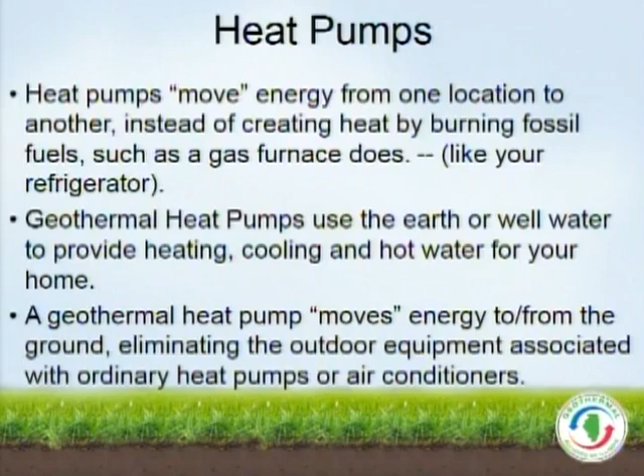In a geothermal system, think about this in terms of 4 distinctly separate and unconnected circuits. The first circuit is the distribution system, which for most houses is ducting like this, sending air through the home. If you have a radiant heat home, it would be pipes installed in the floor. So it could be fluids, or it could be a water-to-air distribution circuit for ducts. That's system 1.